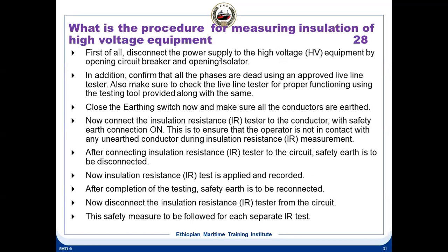First thing is to disconnect the power supply to the high voltage equipment. That means if you want to take a generator stator winding insulation resistance, how do you do that? Or a motor winding, let's take the generator itself. Disconnect the power supply to the high voltage equipment by opening the circuit breaker and opening the isolator. So first you open the circuit breaker, then take the breaker out. Then in addition, check that all the phases are dead using an approved line tester.